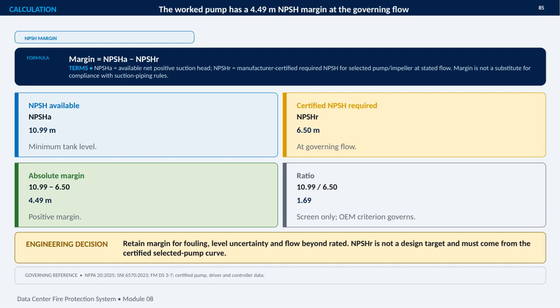The calculation is straightforward. NPSH margin equals NPSH available, or NPSHA, minus the certified NPSH required, or NPSHR. Using the minimum tank level, NPSHA is 10.99 meters. The selected pump and impeller require 6.50 meters at the governing flow. Subtracting those values gives an absolute margin of 4.49 meters, which is positive. The ratio is 1.69, but that figure is provided for screening only. The OEM certified criterion for the selected pump governs the final decision.